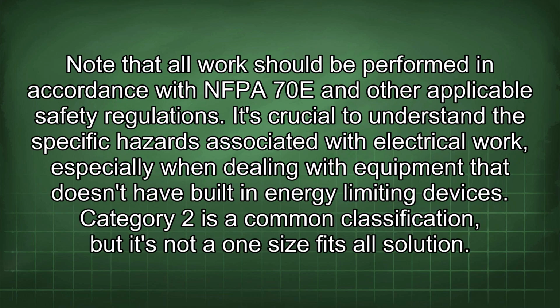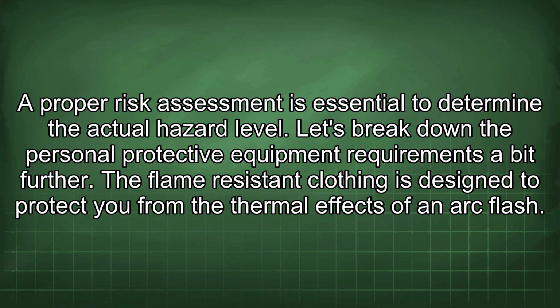Note that all work should be performed in accordance with NFPA 70E and other applicable safety regulations. It's crucial to understand the specific hazards associated with electrical work, especially when dealing with equipment that doesn't have built-in energy-limiting devices. Category 2 is a common classification, but it's not a one-size-fits-all solution. A proper risk assessment is essential to determine the actual hazard level.